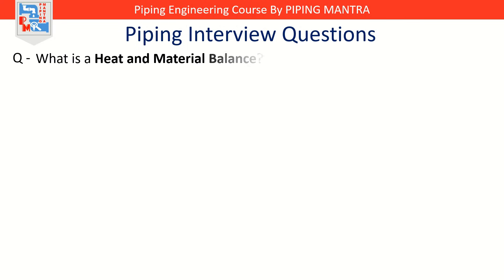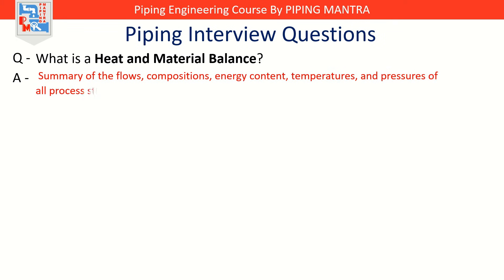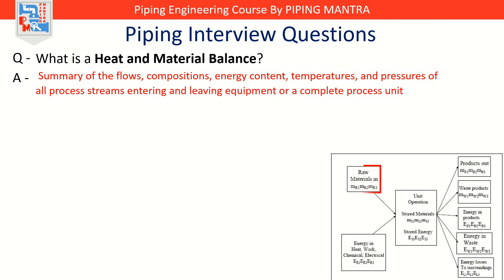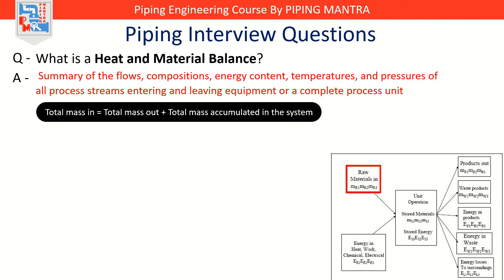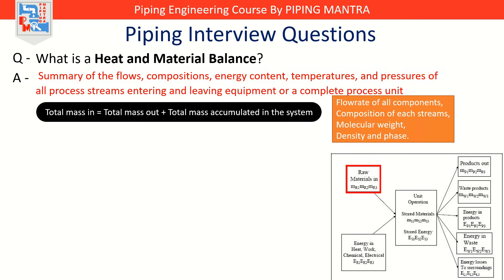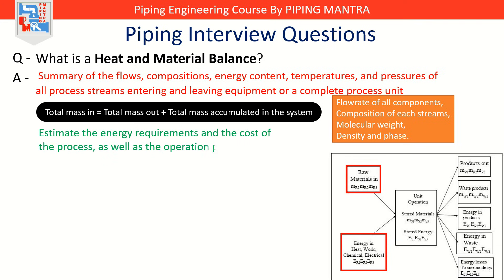That brings us to a tool that process engineers cannot live without — the Heat and Material Balance. What is the heat and material balance, or HMB? A heat and material balance is like the financial statement of a process — instead of tracking money, we track mass and energy. It is a quantitative summary of the flows, compositions, energy content, temperatures, and pressures of all process streams entering and leaving equipment or a complete process unit. The mass balance equation is: total mass in equals total mass out plus total mass accumulated in the system. In mass balancing, we look at flow rate of all components, composition of each stream, molecular weight, density, and phase. In fact, no process will work unless the heat balance is met.